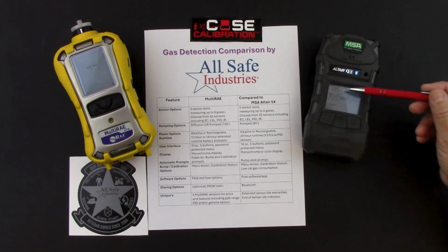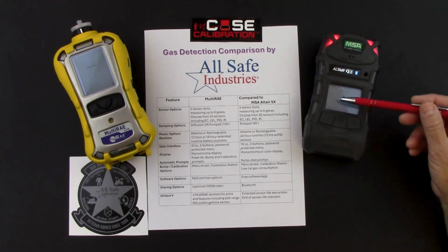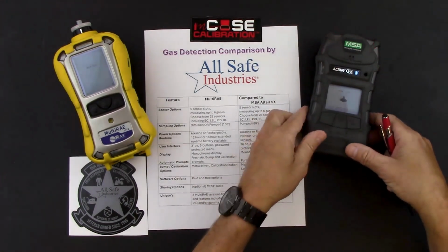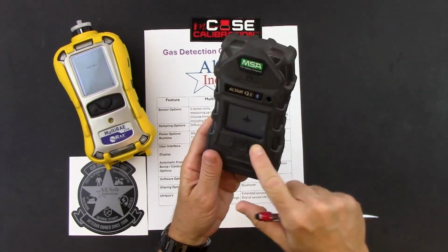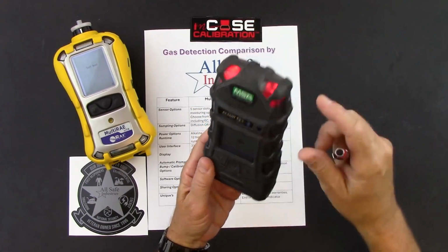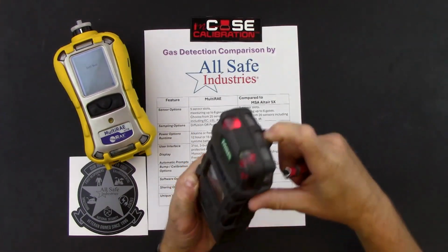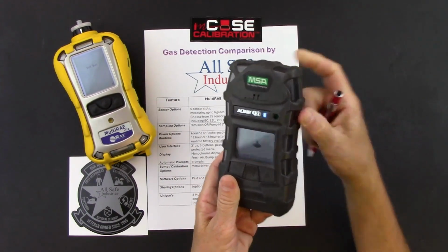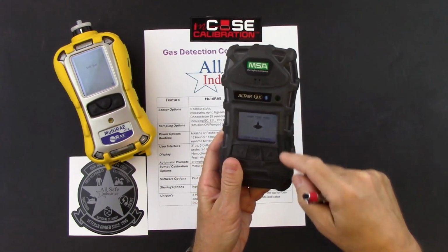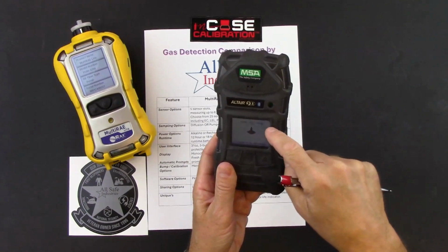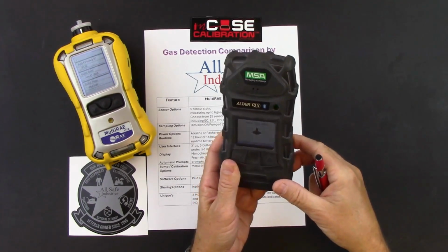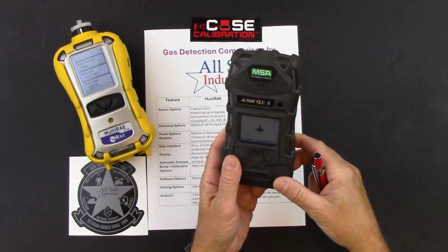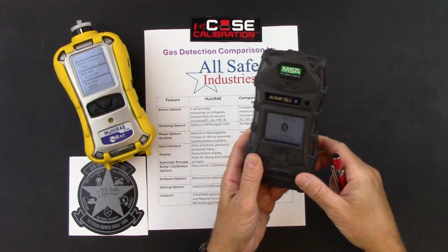It's giving me several details: software version, display, and there's that one and only prompt that we get on an MSA Altair 5X. I have to stall out my pump just to make sure that's working properly. So pump test passed. Pump flow was blocked, pump test passed, and now it's going to go right back into doing its warm-up sequence.